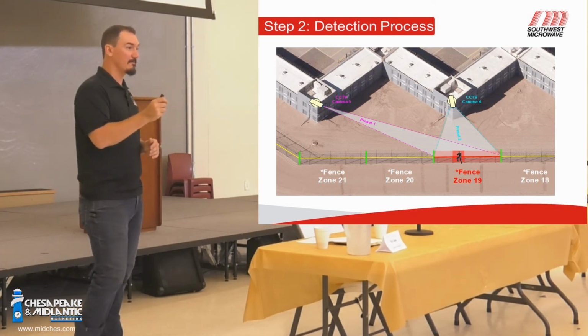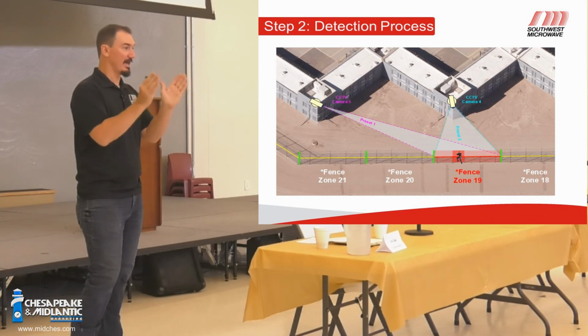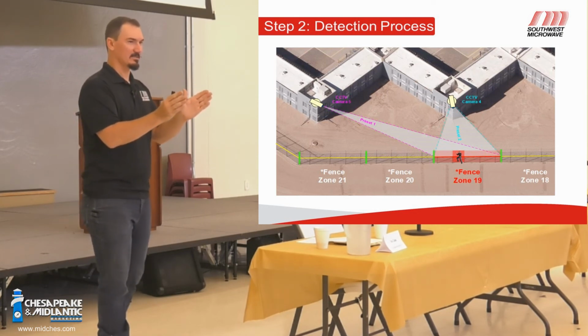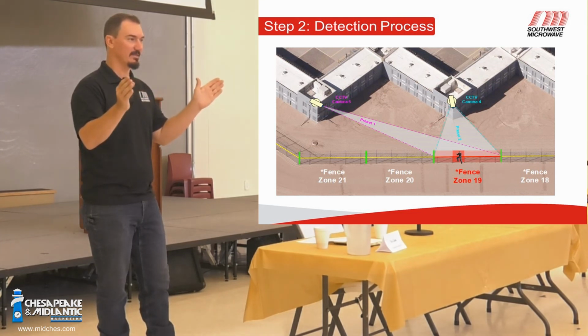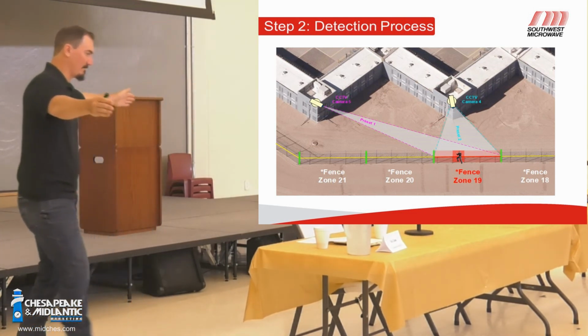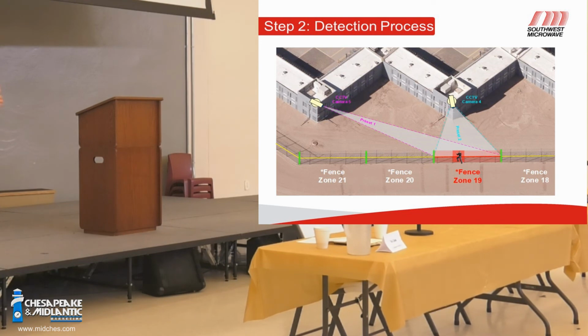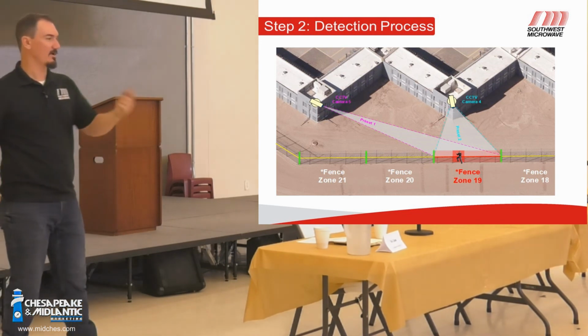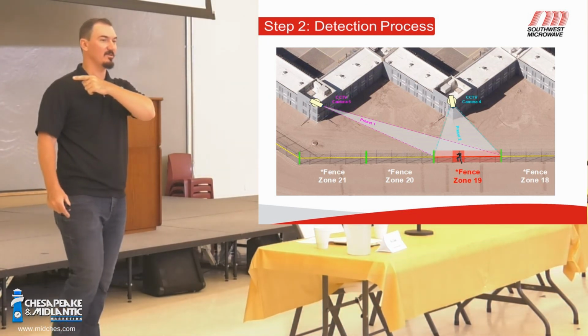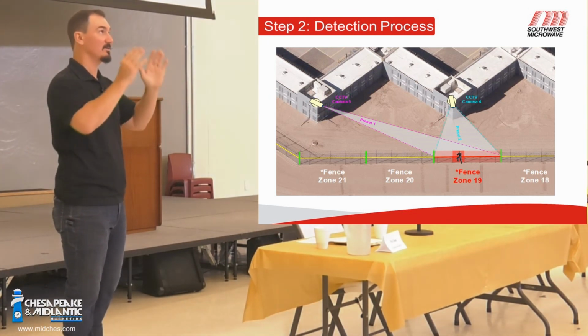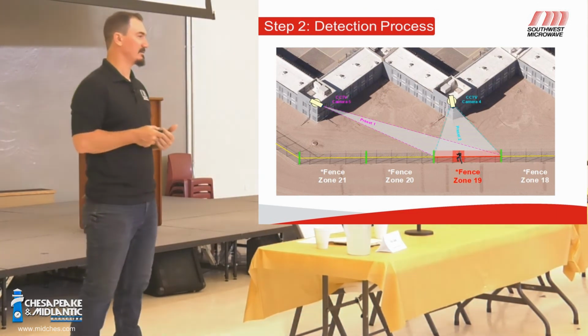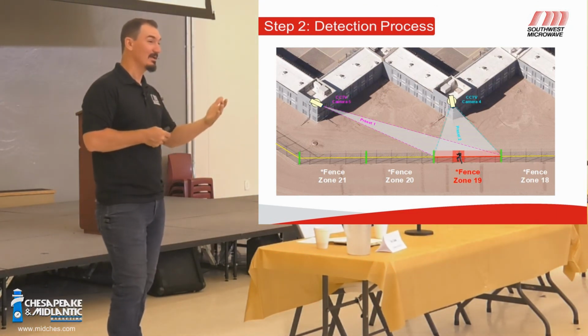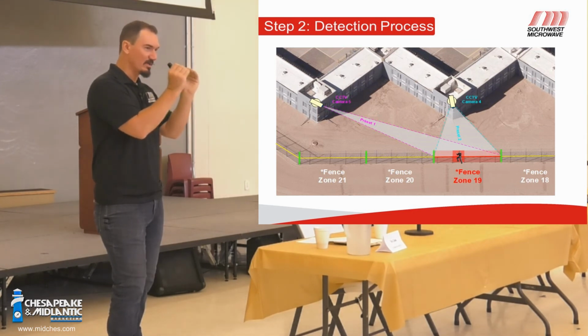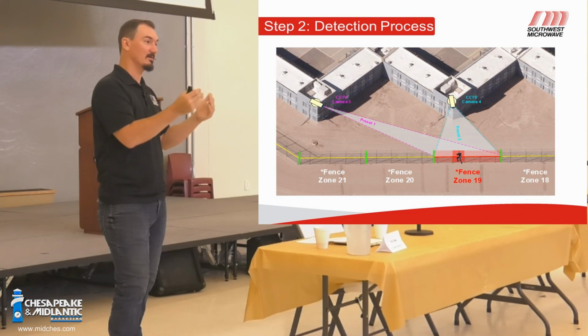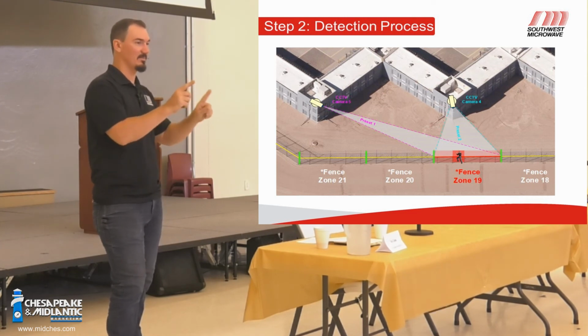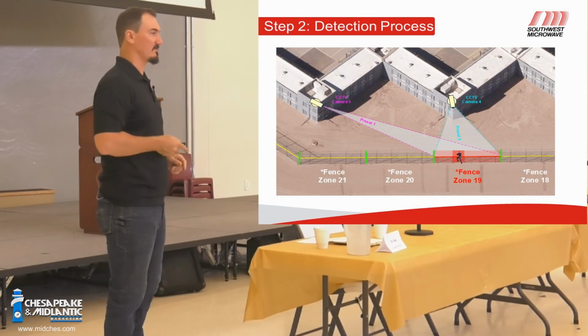When you look at that zone, the camera view should be greater than the actual zone. Does that make sense? You always want your camera view to overlap. If this is my zone here, I want my camera view to be that. And the reason behind that is, if someone bangs on that fence and then runs, you still want them to be in view by the time that camera's turned and looked at them. By the time the guards look up, or the operators look up at that monitor, you want to be able to see that. So if your camera views are really tight on those zones, you might want to consider backing them up a little bit, widening them a little bit to make sure there's good overlap. These are good practices for using the fence or buried systems.